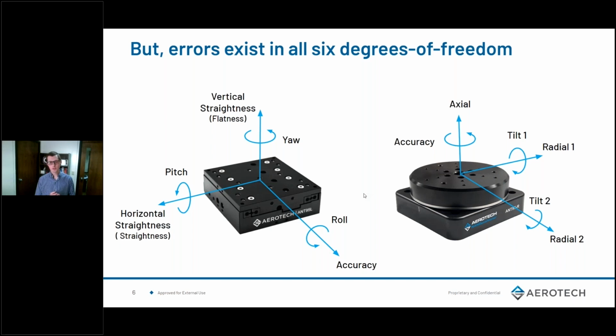Now, motion suppliers should also know the repeatability of these errors. For example, if I move back and forth and move to the same point over and over, there will be some distribution to the vertical straightness that we can measure. That would be the repeatability of the vertical straightness or the repeatability of the flatness. These are typically not posted on suppliers' websites. However, they should know these and be able to use them to estimate calibrated performance of stages. We'll talk a little bit more about this as we go into the case study toward the second half of the presentation and how this would affect your optical alignment.